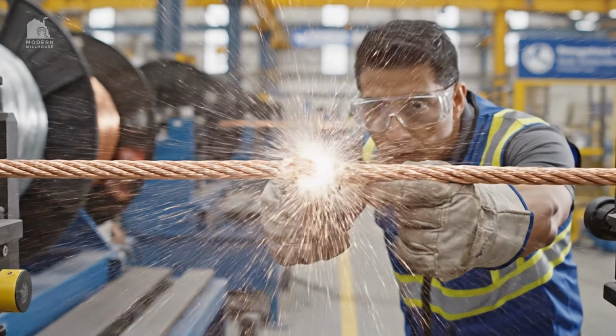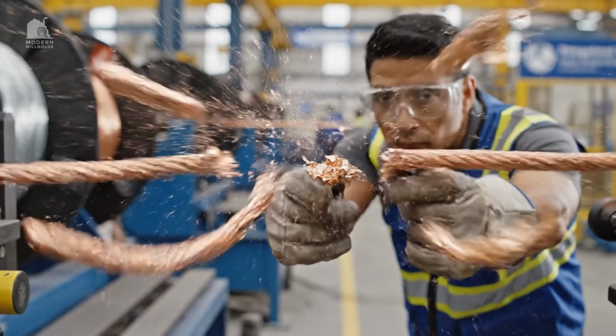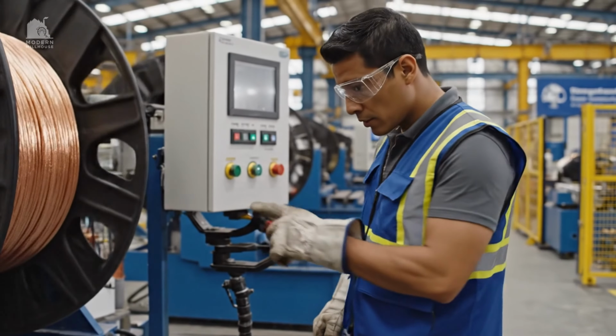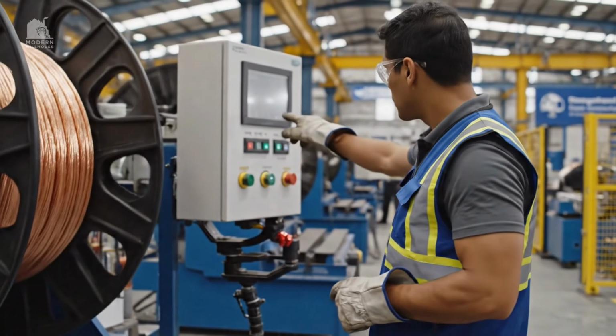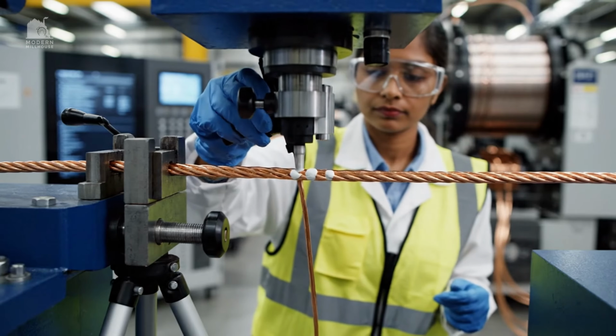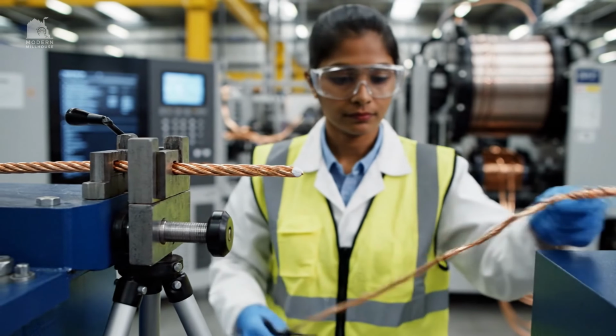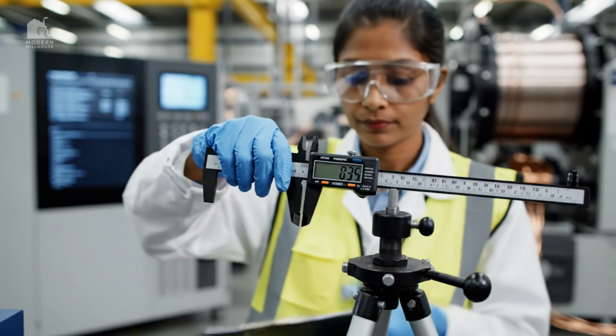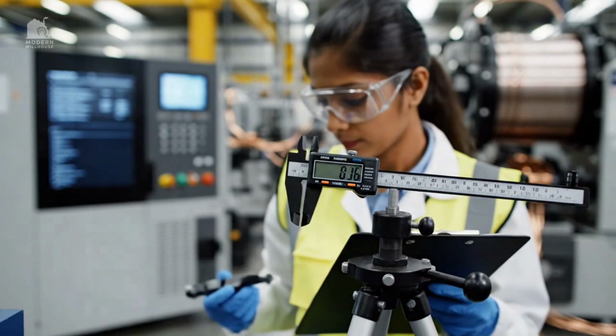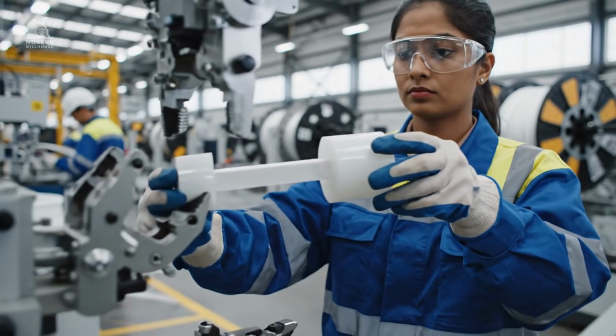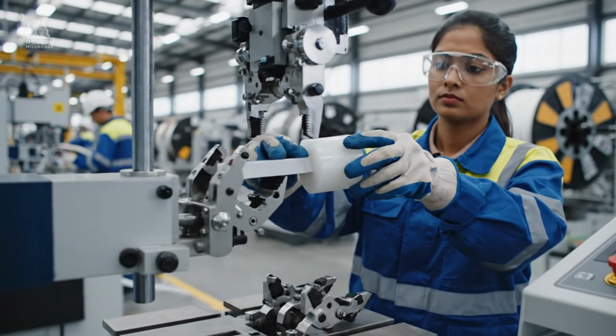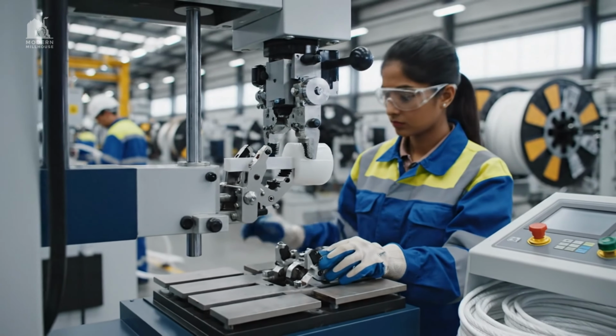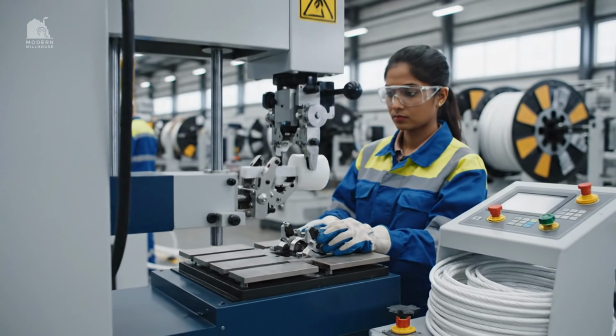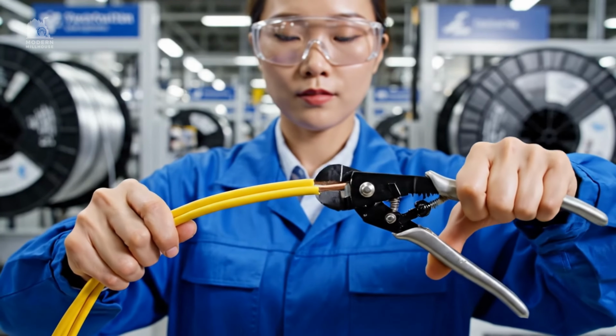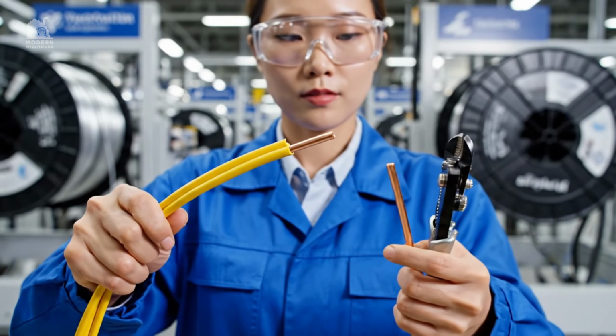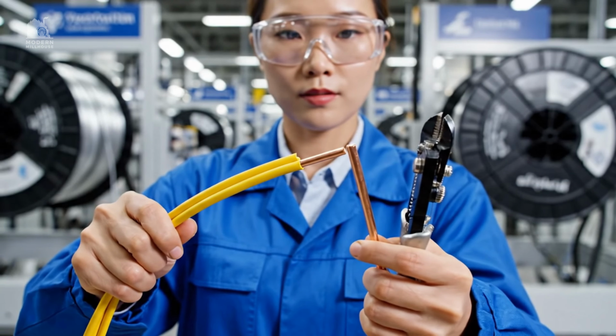A clean, predictable break suggests proper annealing. Brittle fracture can signal processing problems. Elongation shows ductility. Too low means brittle copper. Too high can mean over-annealed softness. Insulation is tested too, because polymer that turns brittle can crack after years of heat exposure. Strip behavior matters. Insulation must hold firmly, yet remove cleanly during termination.